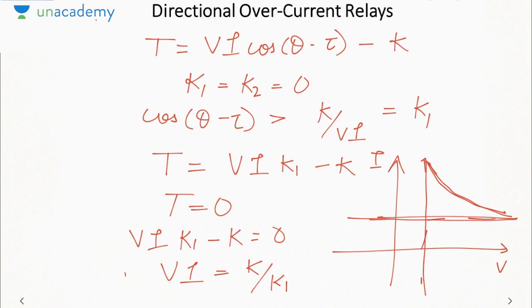If it were only the directional relay, then there would be no minimum limits for the voltage and current. But it has an overcurrent unit, so we need a current greater than the pickup current for it to operate. And remember, in directional and overcurrent units, priority is given to directional. That means once the directional unit of this relay operates, only then will the overcurrent unit come into the picture. If the direction of current is not reversed, no matter how high the current flowing in the system, the relay will not operate. Once the direction is reversed, it will check the magnitude of current. If it is found greater than the pickup current, it will operate. Otherwise, it will not operate. So remember, first direction, then magnitude.